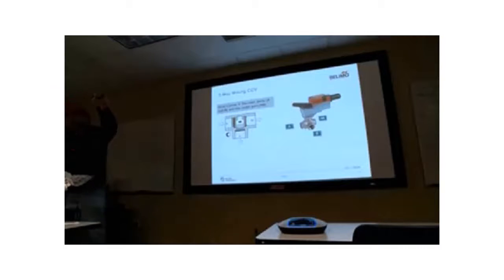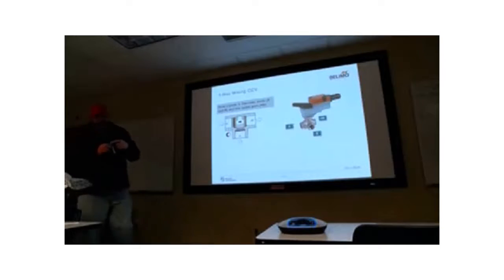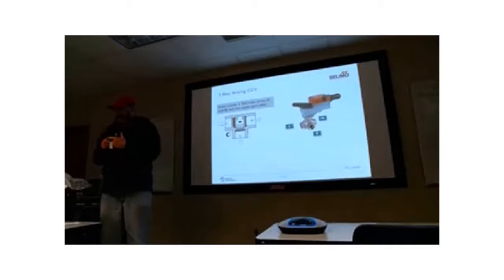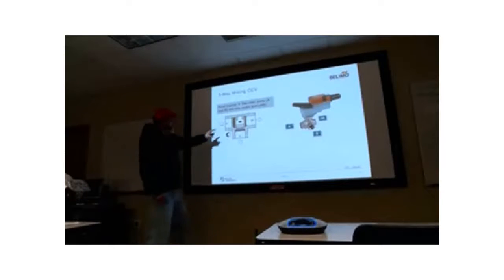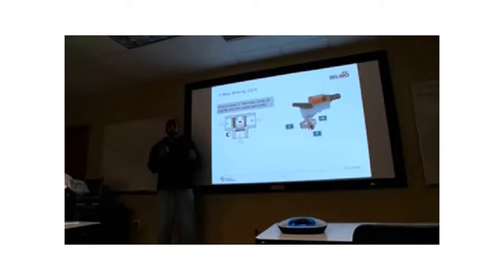This is a 3-way valve. This is that 3-way CCV. And you're going to see a bunch of these in your lifetime if you stay in service. If you look in the top of this, I'm going to pass this around, you can see it. If you look in the top of this stem here, you're going to see slots in the stem. Remember, those slots tell you where these ports are. So you could take the actuator off and say, okay, I know where the ports are, right?